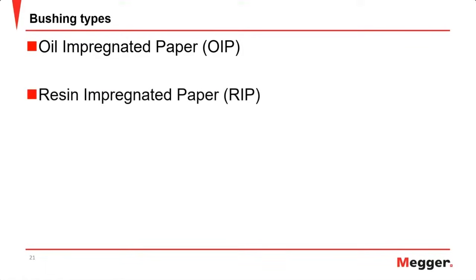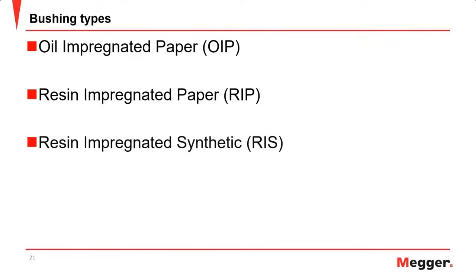The next type of bushings, instead of using oil, is going to use resin. So this is resin impregnated paper. This is where a vacuum is pulled and then resin is pulled into the gaps within the paper itself, and then it's allowed to cure over time, and it creates a similar insulation system. Next, we have resin impregnated synthetic. This is a woven material that is intended to have better heat withstand capabilities than paper itself, but the process is the same as resin impregnated paper, where again, we're not using oil, we're using a resin that's pulled under vacuum, used to fill in the voids in the synthetic material, and then allowed to cure over time.